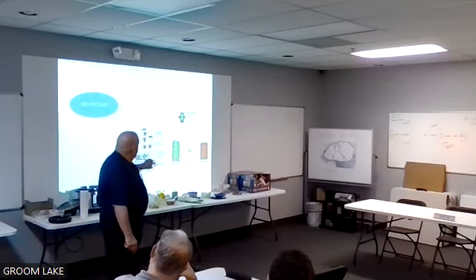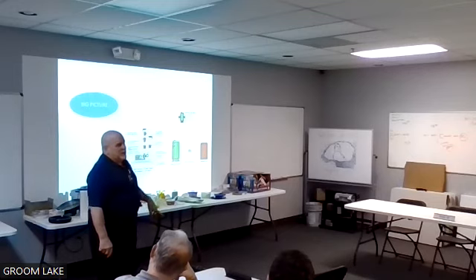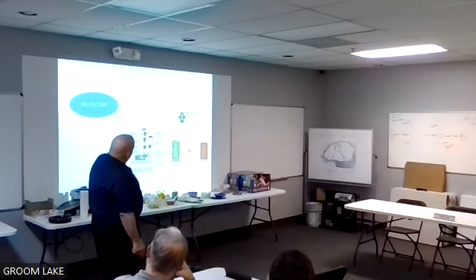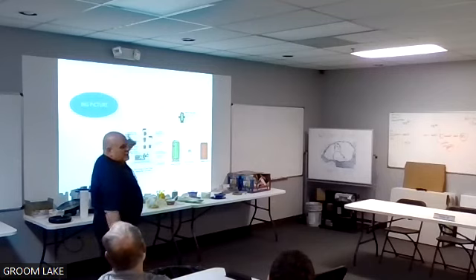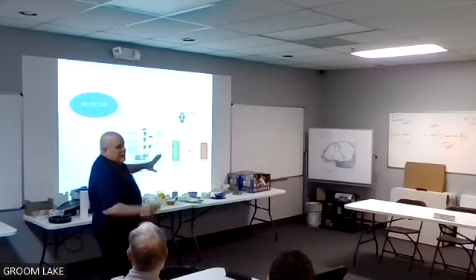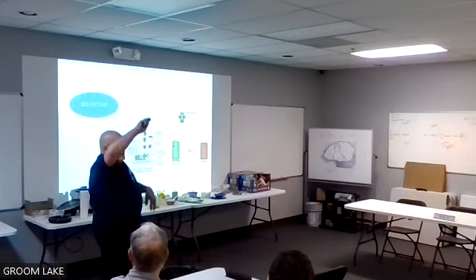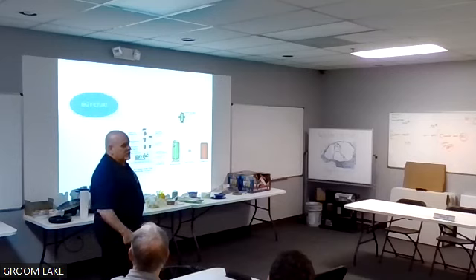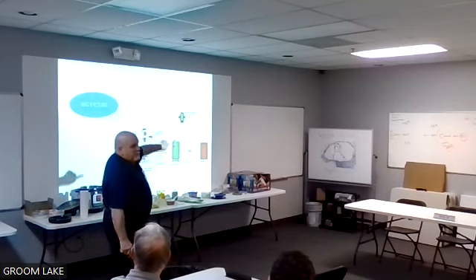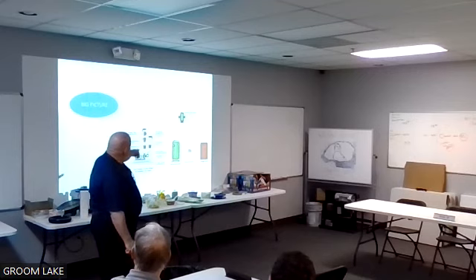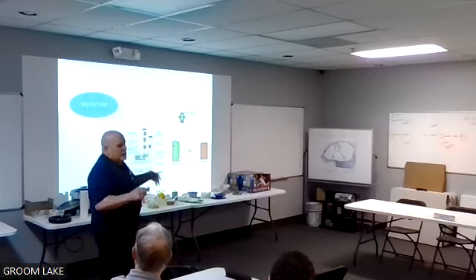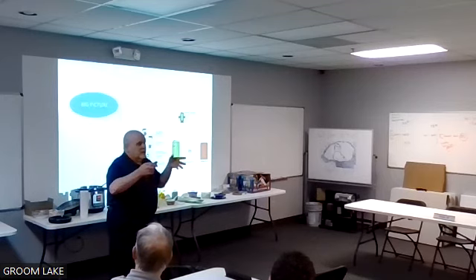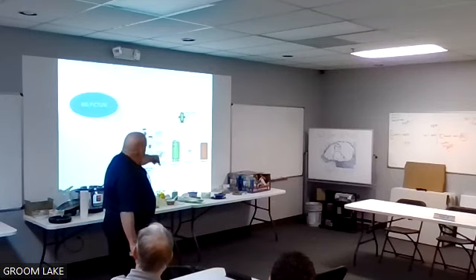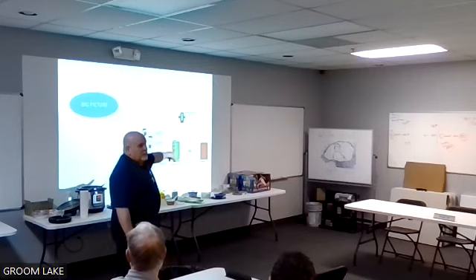The reason being that's the point of no pressure change. If my pumps are sized correctly, by the time they come on and run that loop, I've exhausted all that extra head that's been supplied by that pump, because up and down, we don't do any lifting with pumps. All we're doing is overcoming friction. So if I run all the way out and back, I've exhausted all the head. So the pressure at the suction side will stay fairly constant. Whatever your fill pressure is, it'll only go up as the water expands. So that's why you want to put it there.